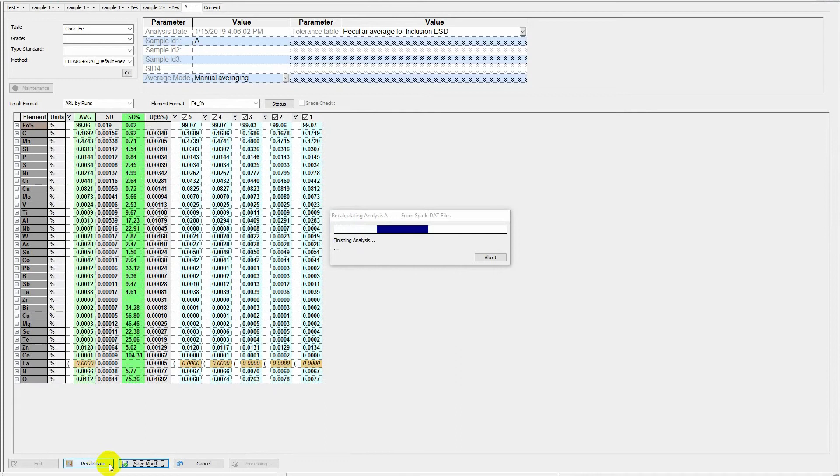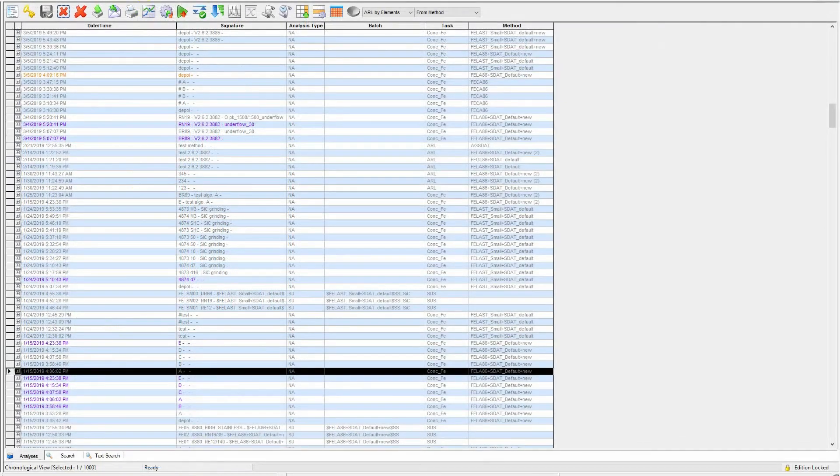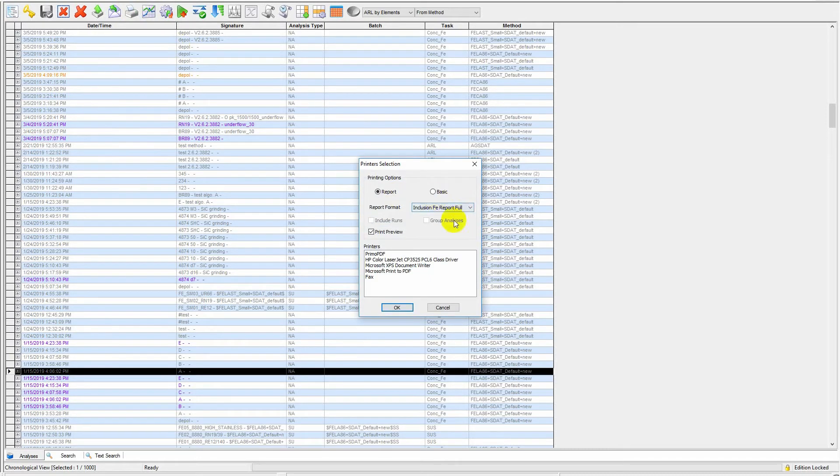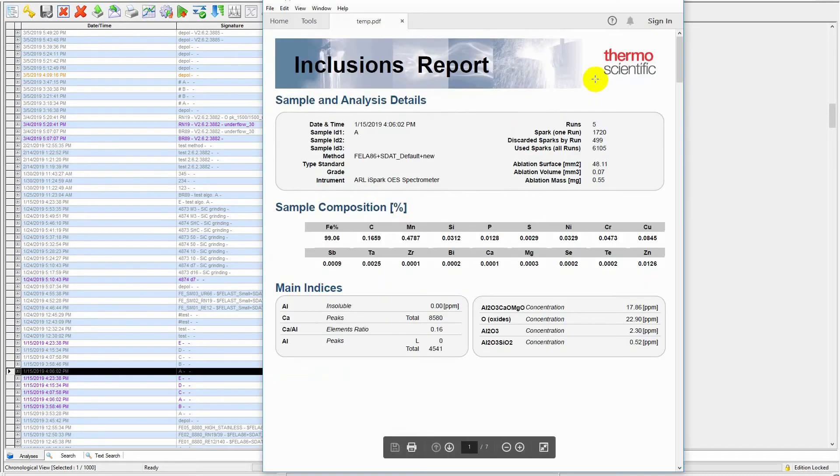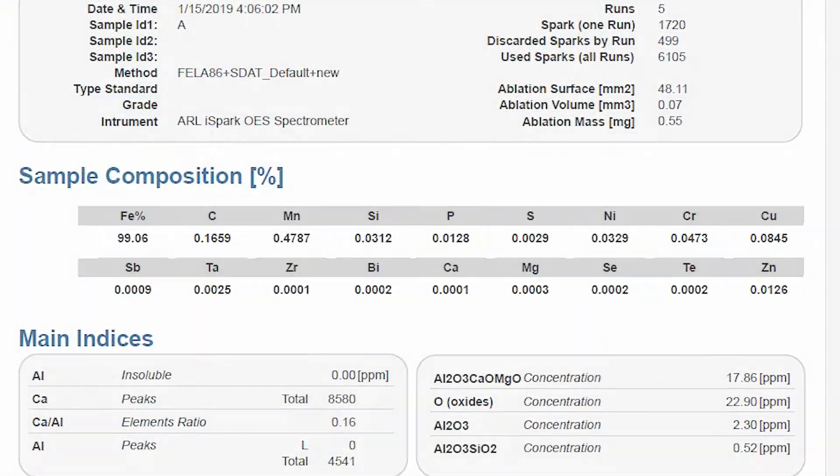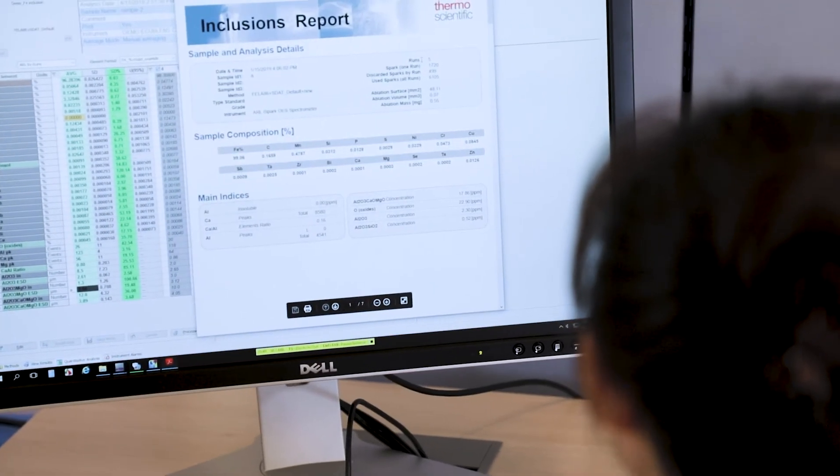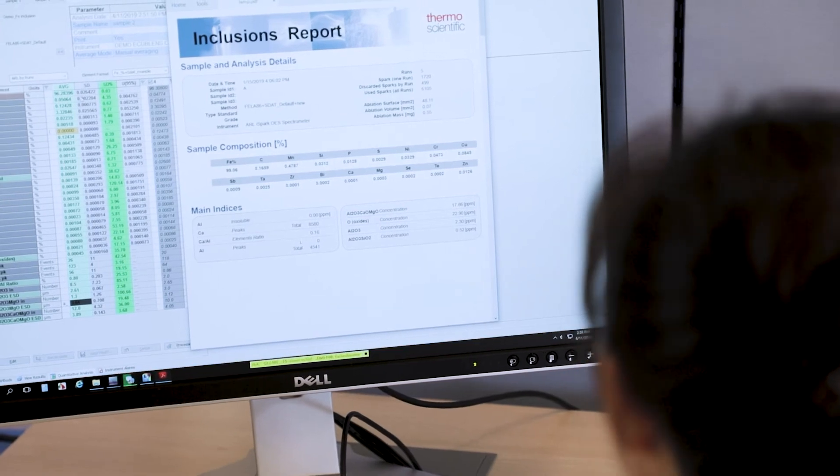Optional methods using the SparkDAT algorithms allow ultra-fast analysis of micro-inclusions, for example, aluminum oxides in steels or titanium diboride in aluminum. The inclusion analysis can be performed simultaneously with standard OES analysis without any change in operation or maintenance.